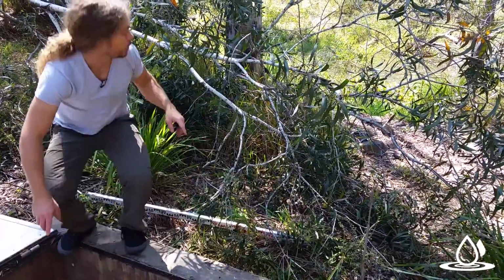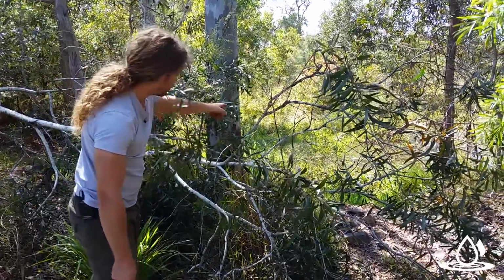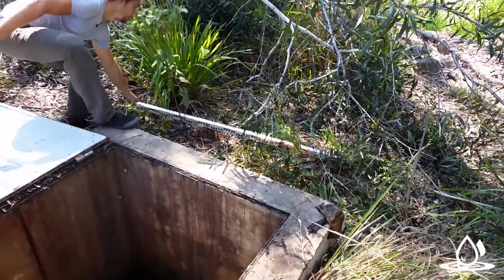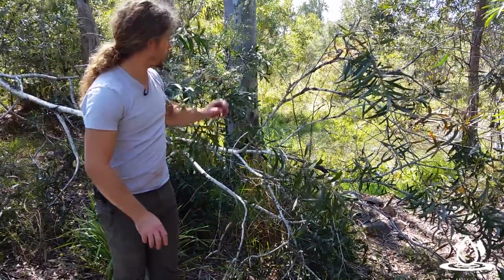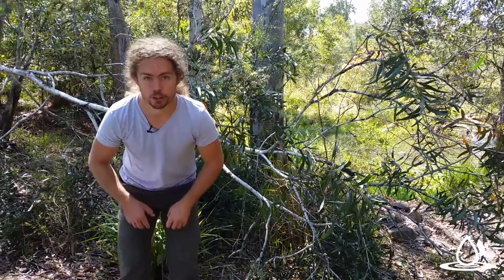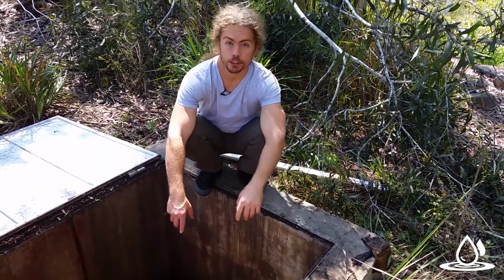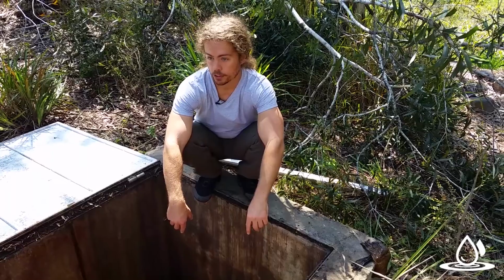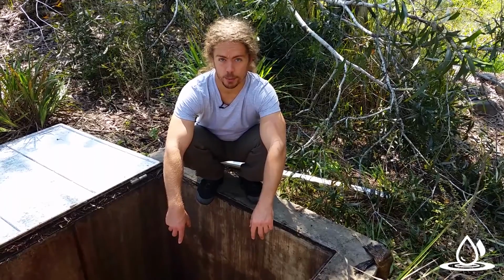In this case, we can see the wetland right just through there. We kind of eyeballed this initially and we thought, oh, we think the water level down in the pit here is the same as that water level there. We then got out the survey staff and the laser level, and we checked it. And indeed, the water level in the pit here and the water level in the downstream environment are very, very similar. We couldn't get a lot of accuracy on it, but we're confident that they're the same. So we said, okay, we've got a bit of a backwater issue from that downstream environment, and that can start to inform what we think about, is the water level appropriate back up in the wetland? And that's essentially how we go and investigate a pit.